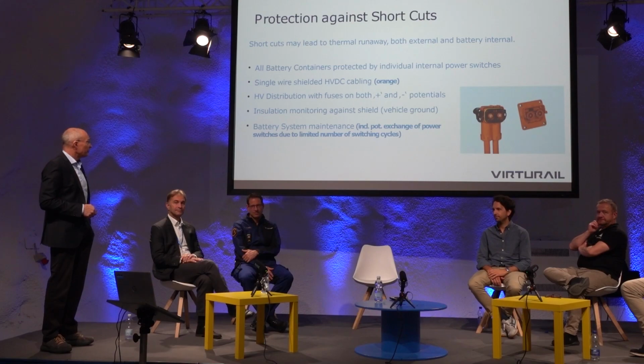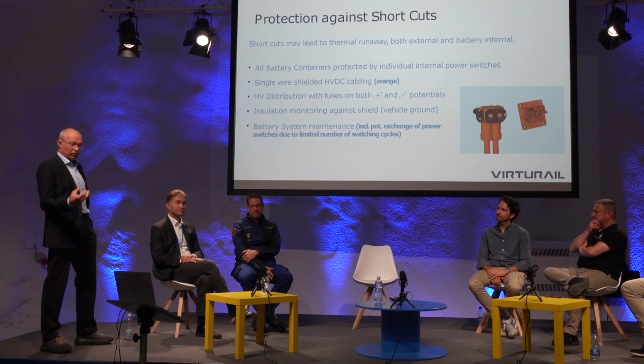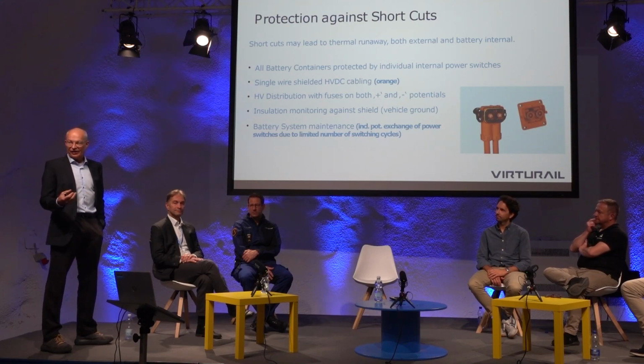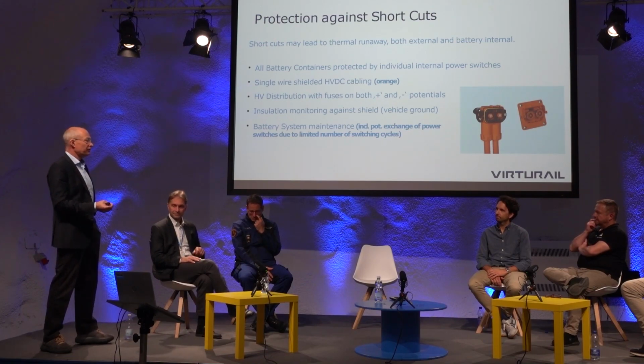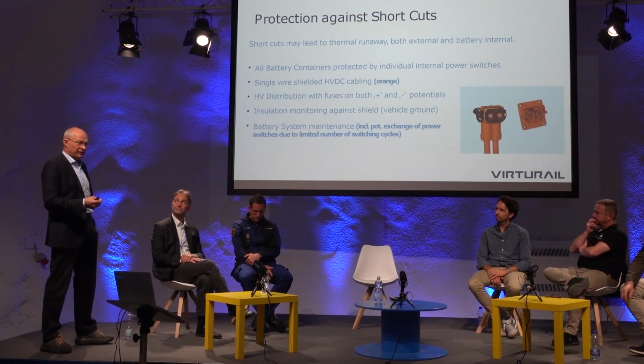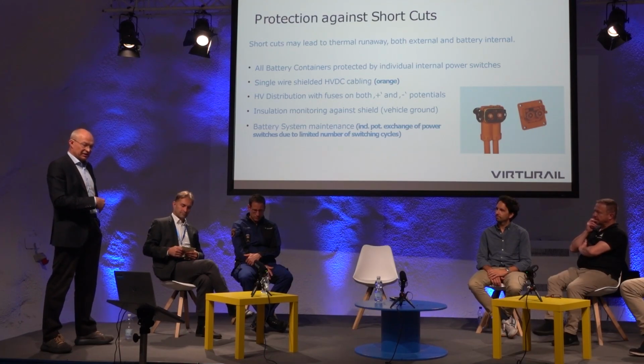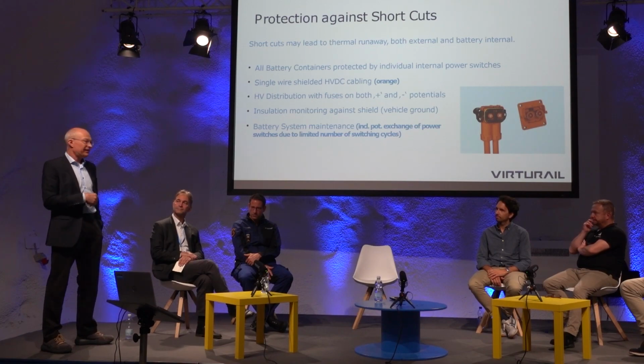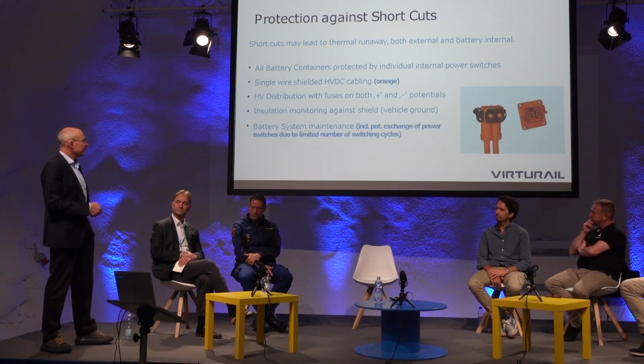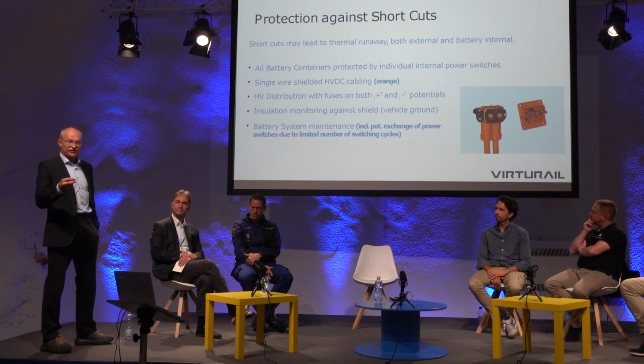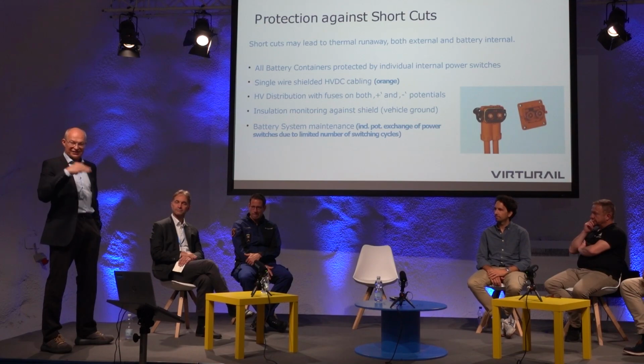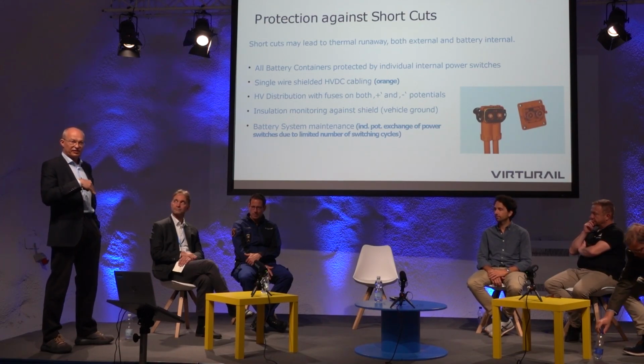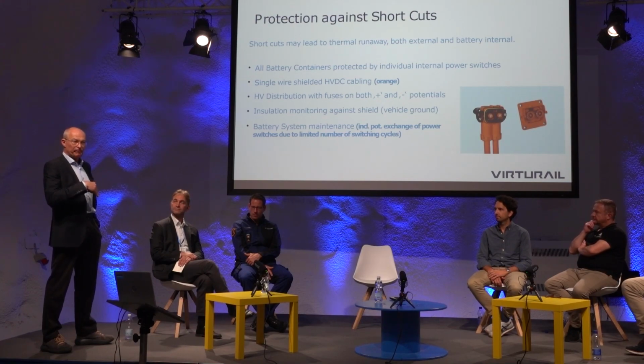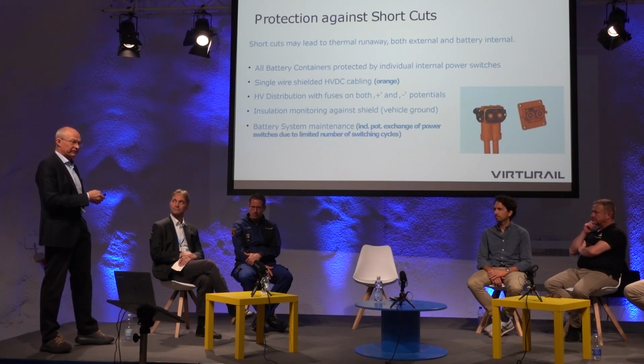The other point is that the internal power breakers of the batteries have a limited lifetime, a limited number of cycles they can be switched under load. And if you have emergency stop conditions, when the battery breakers suddenly have to dump the load, they wear down very quickly. This needs to be taken care of in maintenance, because if such a power switch is hanging in the on position, you suddenly get the high voltage system powered while you think it is unpowered. This is a dangerous situation.